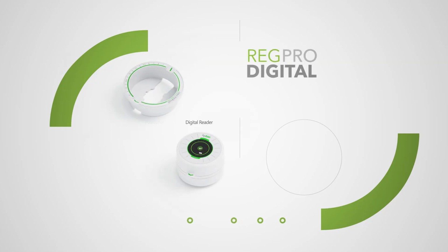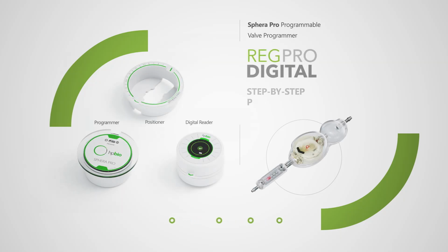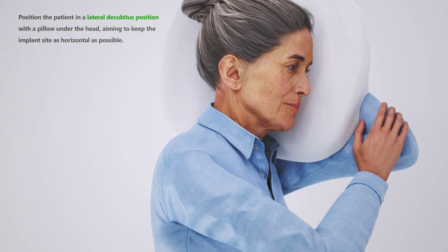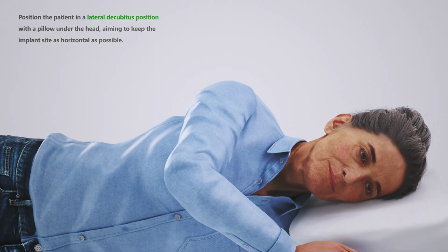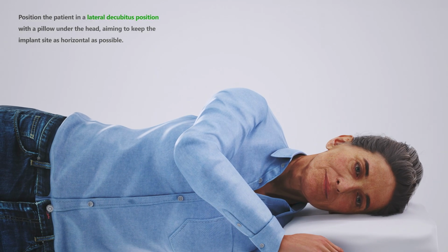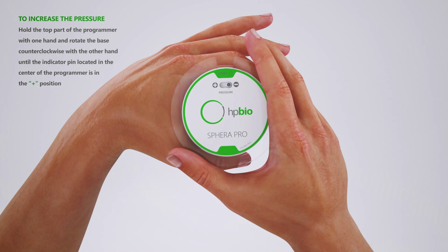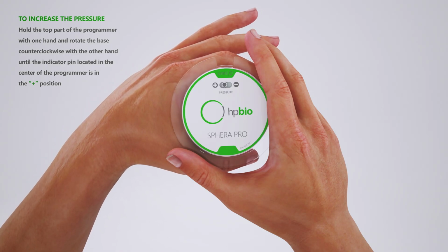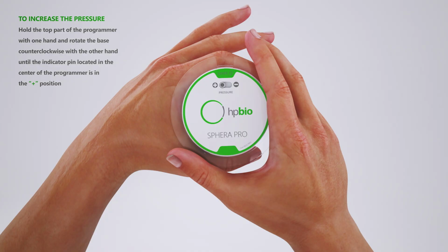SpheraPro valve programming procedure with the RegPro digital device. Position the patient in a lateral decubitus position with a pillow under the head, aiming to keep the implant site as horizontal as possible. Prepare the device for the procedure. To increase the pressure, hold the top part of the programmer with one hand, and with the other, turn the base counterclockwise until the indicator pin, located in the center of the programmer, is in the plus position.